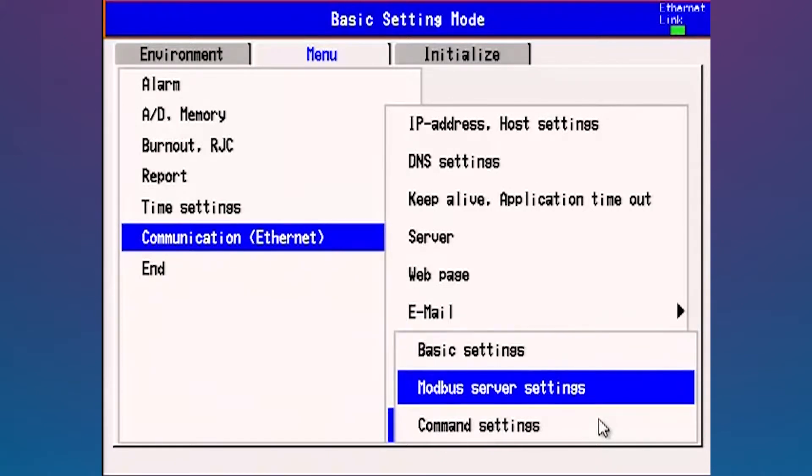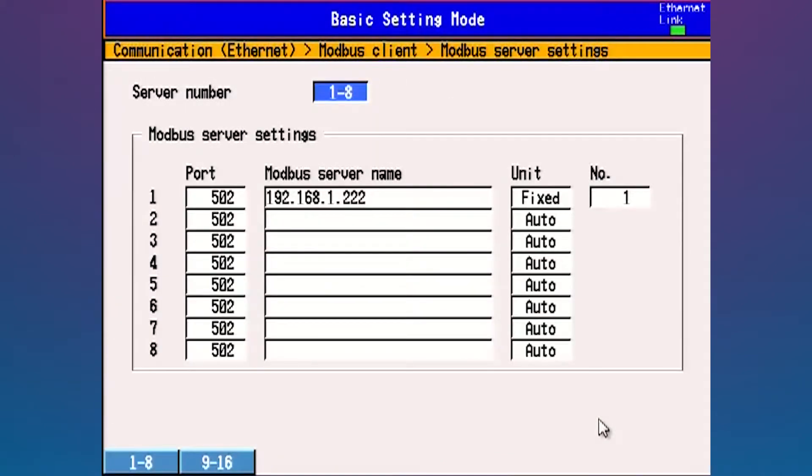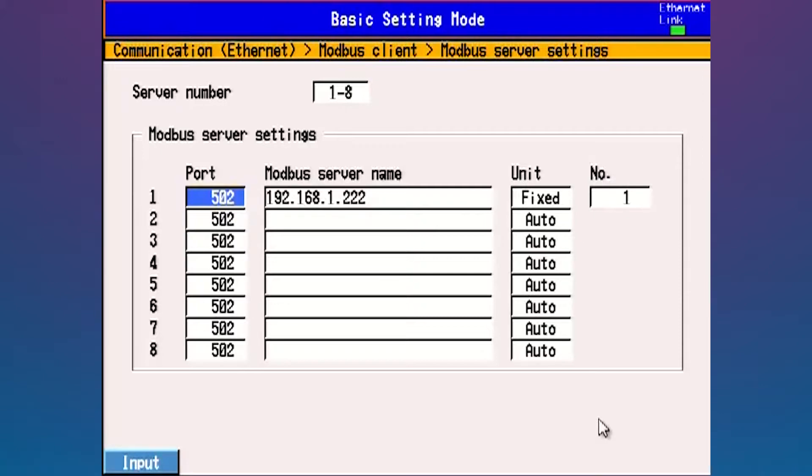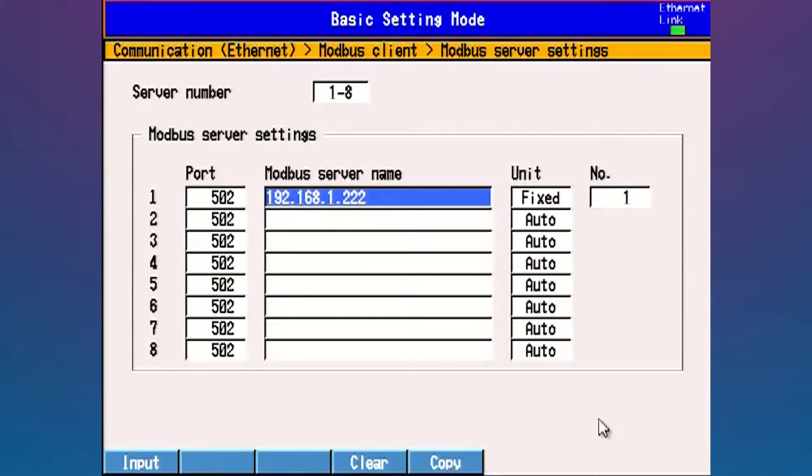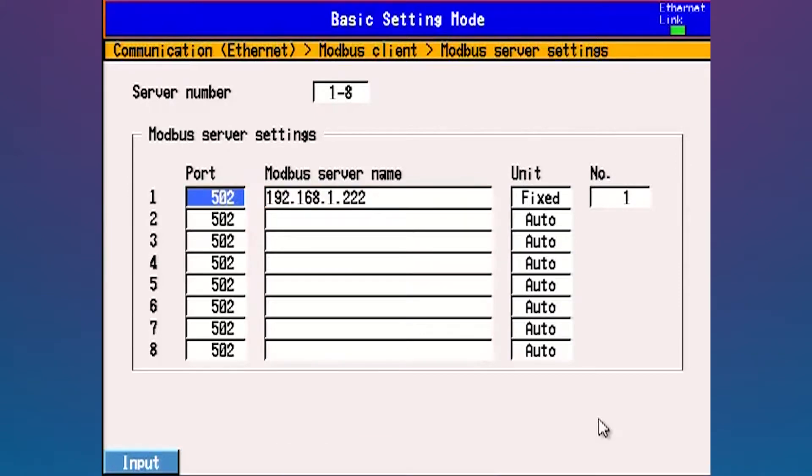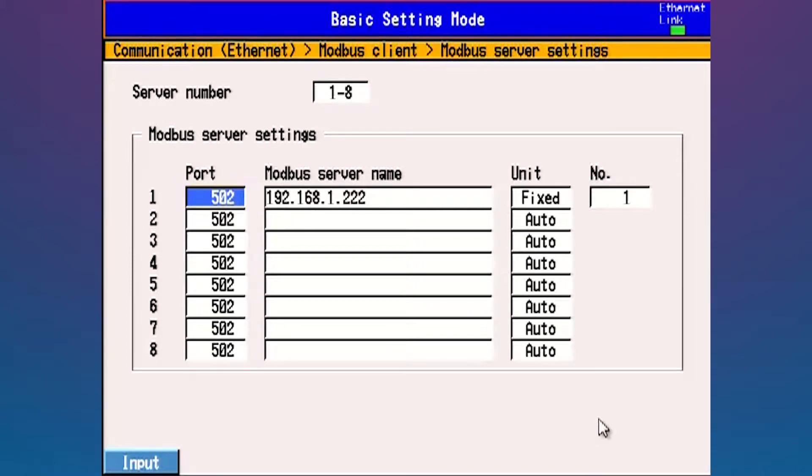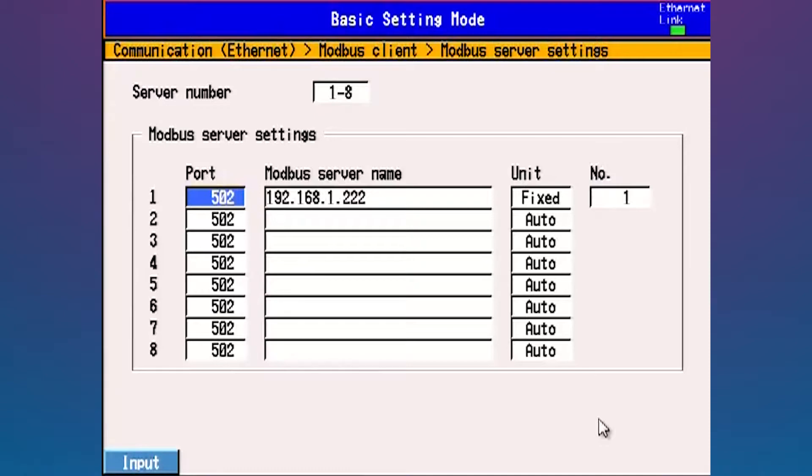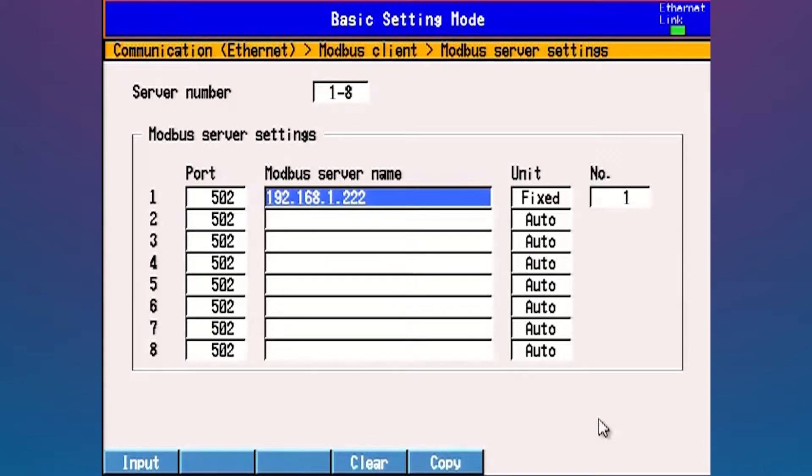Next place we're going to need to go is the Modbus server settings. Port 502, that's a standard port number for accessing Modbus Ethernet protocol. Think of a port number as a doorway into the machine. The IP address is like the street address, the port number is the doorway. It's the thing that MV Advanced is listening to for Modbus Ethernet communications. Port 502 is standard for Modbus Ethernet protocol. If you need to change it for some reason due to security reasons, you got to have it changed on both devices—the MV Advanced in this case and the MW100 on the other end.